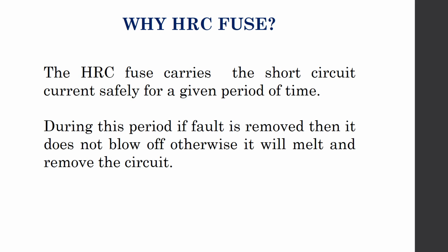So, when the operation of HRC fuse and a normal fuse are quite similar, then why are HRC fuses needed and why are HRC fuses used? The basic difference between the HRC fuse and a normal fuse is that when a fault occurs in a normal fuse, the fault current melts the fuse wire at the same period of time. Whereas in an HRC fuse, the fault current is carried for a given period of time, and during this period, if the fault gets removed, then the fuse wire will not melt and the circuit will not be removed from the supply. But if during that period the fault is not removed and continues, then finally the fuse wire will melt and the circuit is removed from the electrical supply.